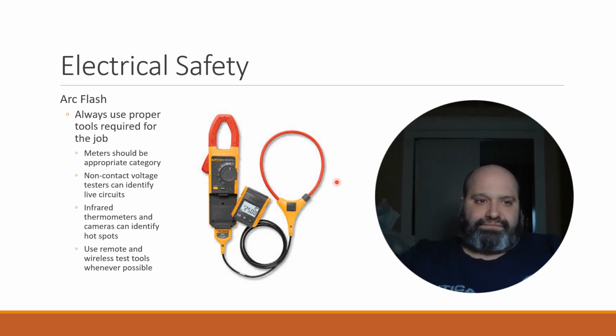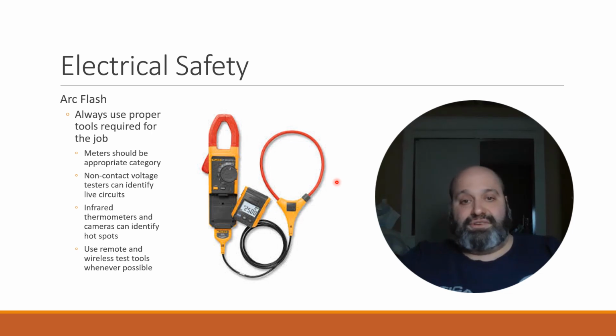You can also use non-contact voltage detectors, which are good for a quick check of whether a circuit is live or not. Infrared thermometers and cameras can help you identify hot spots. So when you're pulling that grounded motor out and it's smoking hot, even your little infrared thermometer, shoot that at the motor real quick and it'll let you know if it's hot or not.